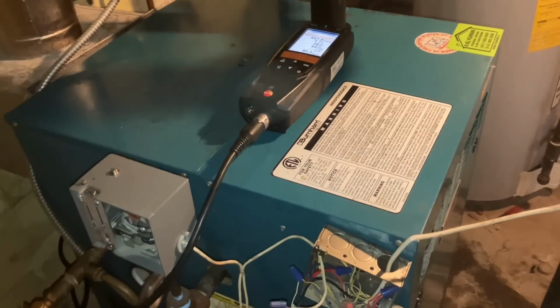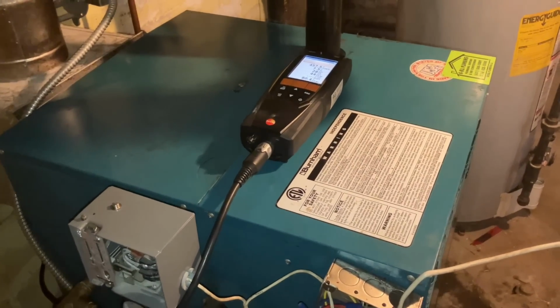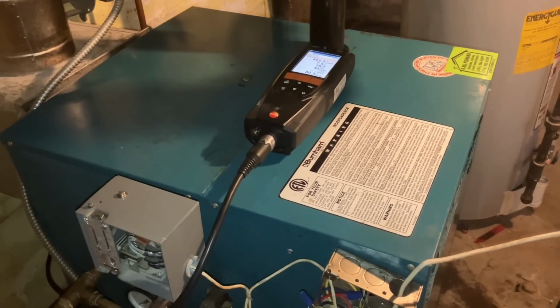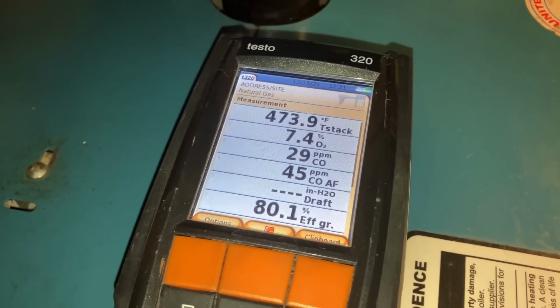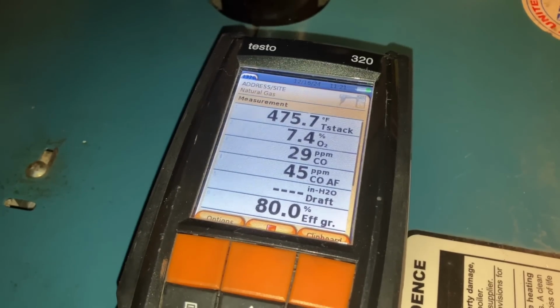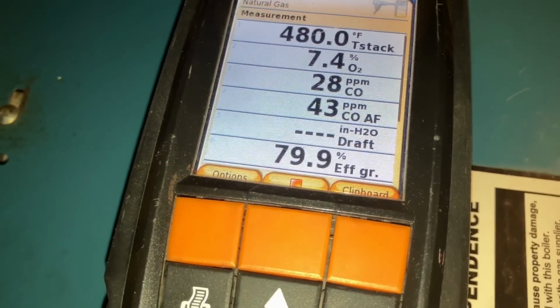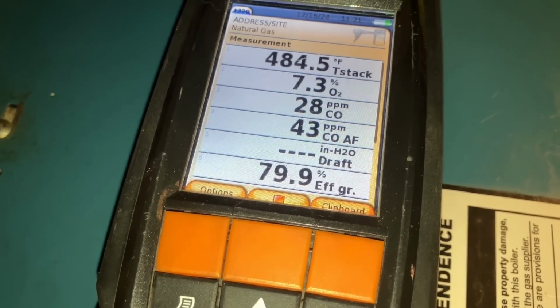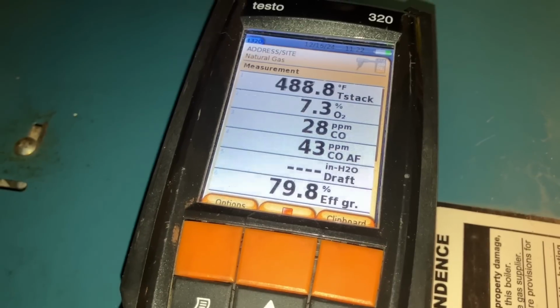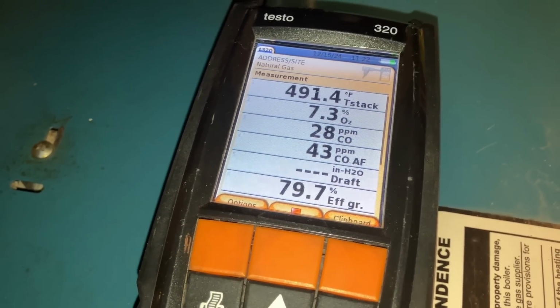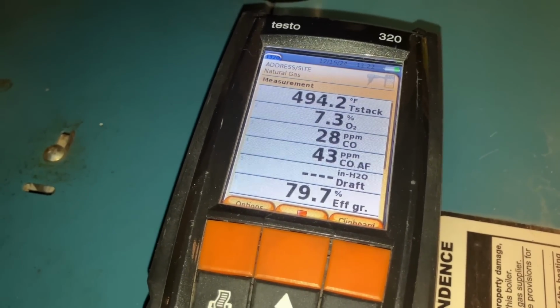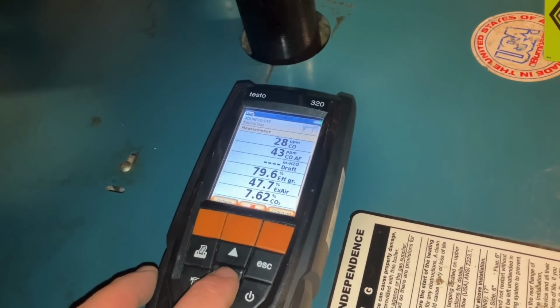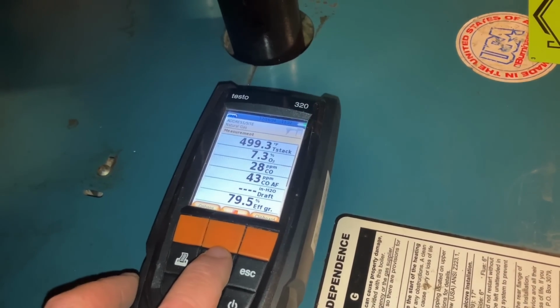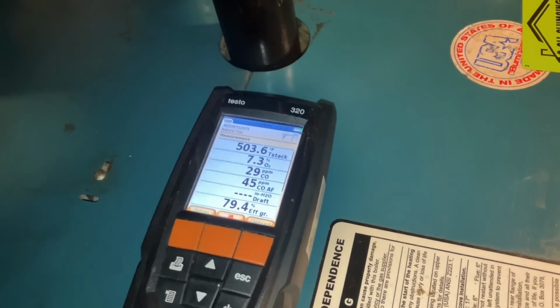An atmospheric steam boiler, which is what this boiler is, will typically be about 50 degrees higher than a traditional hydronic boiler, which is heating water to normally 180 degrees. So if we go much higher than where we're at now, I wouldn't be that surprised. But if we go in the 500 degree territory, our efficiency will suffer. Right now it's 79.9%, and we're at 487 degrees of stack temperature, 489, 491, 492, 493, 494. So we're climbing there, and CO2 7.6. Carbon monoxide 28 and 7.3 of O2.